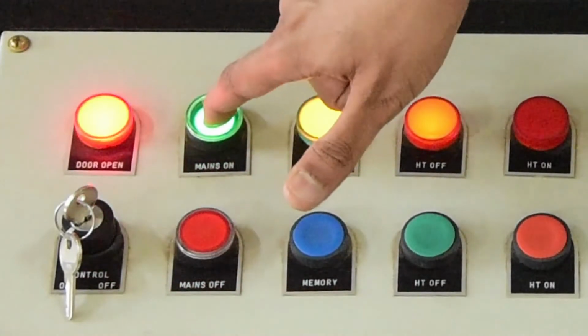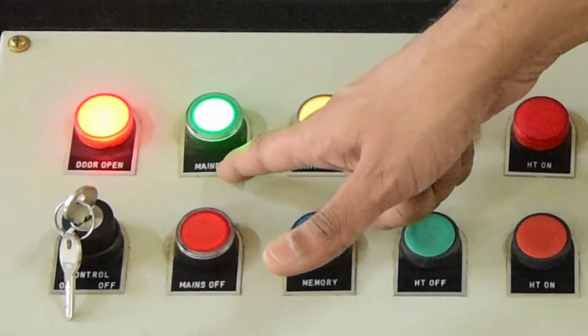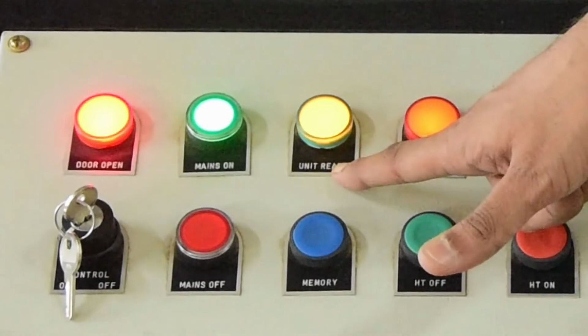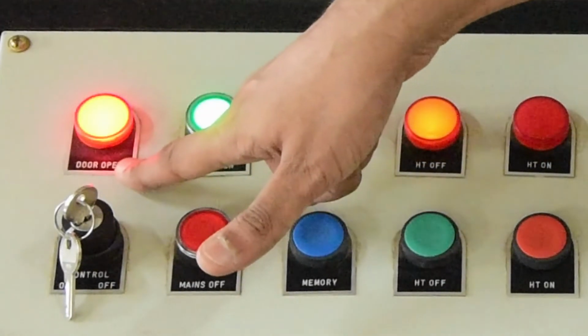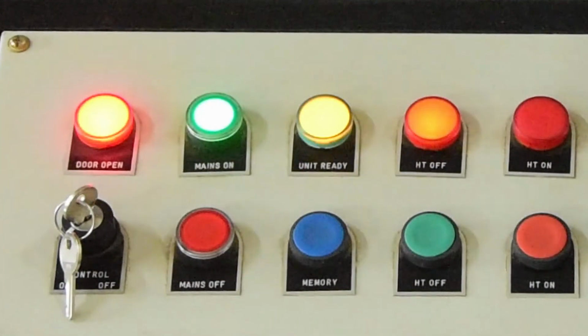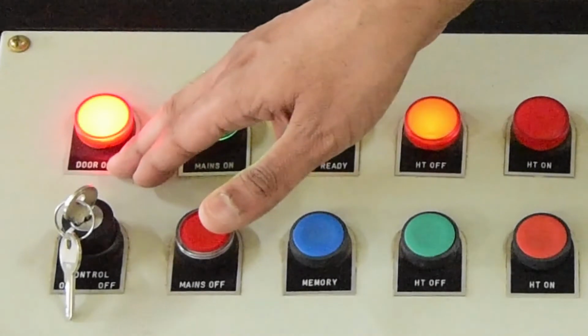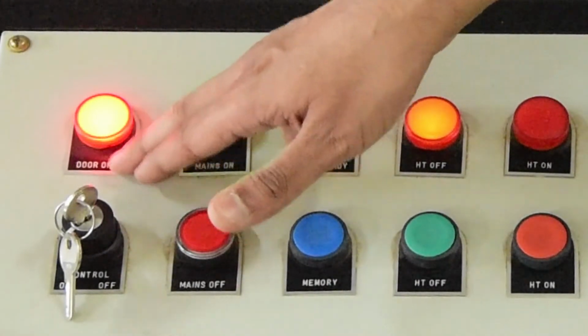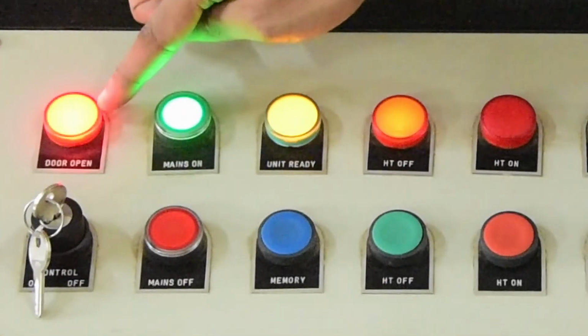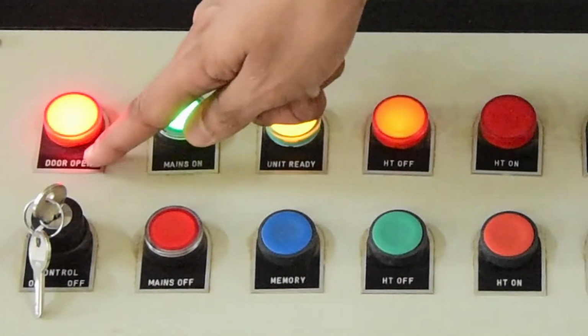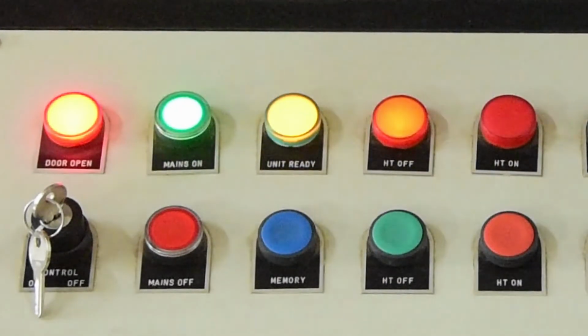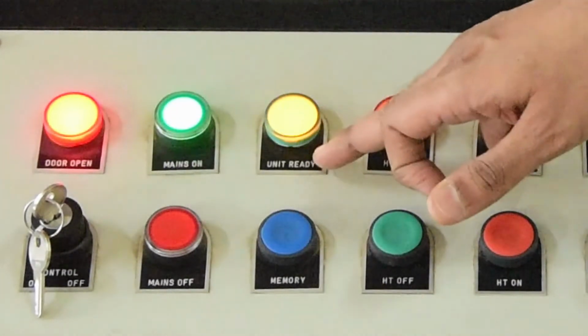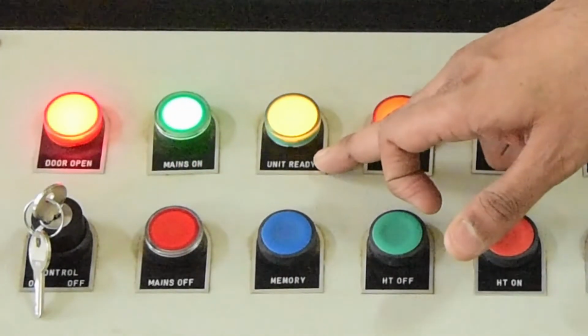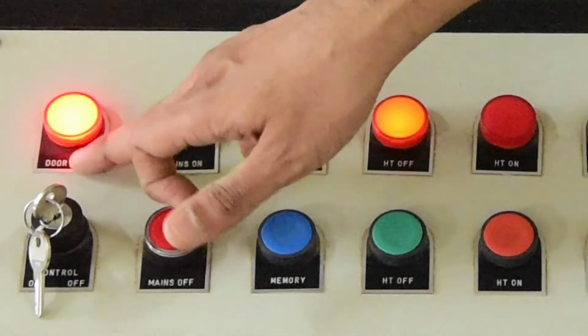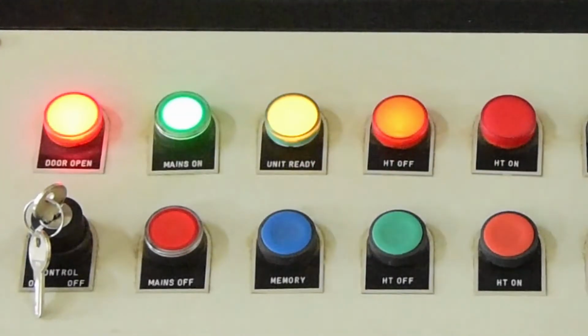Now we put the mains on switch. As soon as I put the mains on switch, it shows that the unit is ready. At the same time, the door open indicator is glowing. The main reason for this is that we have shunted this particular switch, because we have not connected the limit switch to the cage. Hence it is still showing unit ready, because that has been looped out, as no switch is connected at present on the cage. Now let us move ahead.